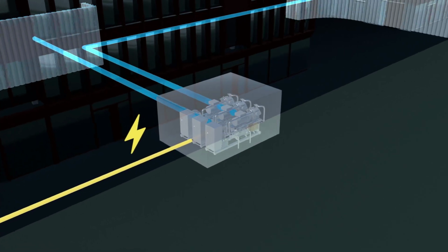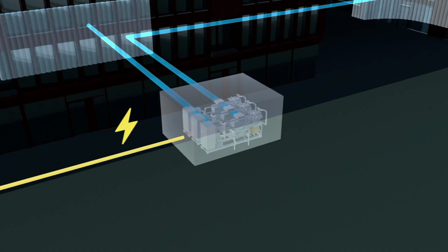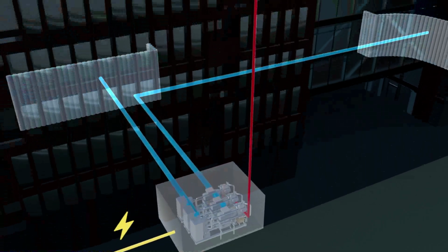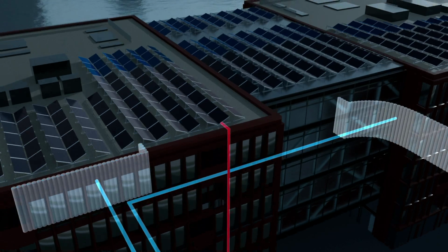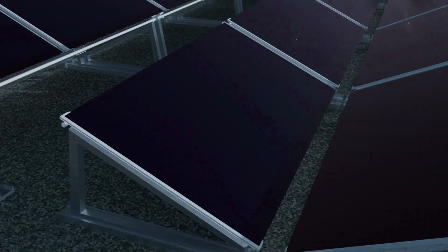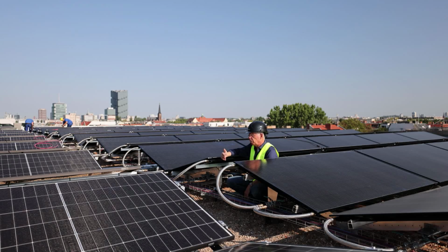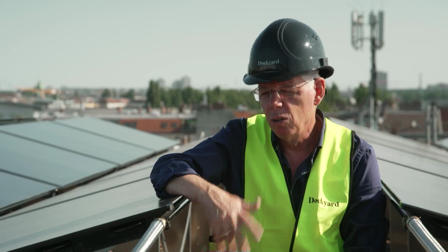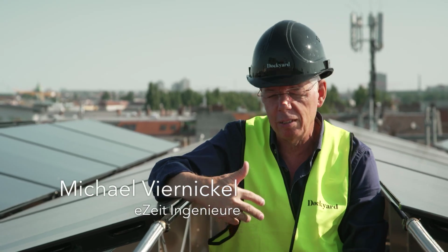The heat then flows onto the roof at night, and the modules are heated up. The heat is then released into the Berlin night sky. And all without heating up the city's climate. In contrast to an air conditioning system, we do not create heat in order to cool the air, nor is our system loud. We emit heat into the sky via radiant heat without causing any noise. There is less noise and less strain on the urban climate, which would otherwise continue to be heated up by conventional air conditioning.